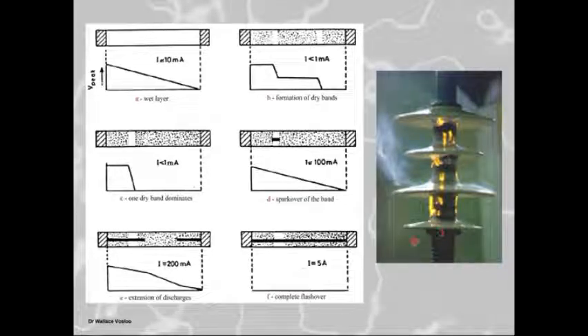But now you've got these little pollution particles which are driven by the wind, and they come boom, boom, boom, and they all start collecting onto this insulator surface. All over the surface, this pollution starts collecting. The wind is the main driver of this pollution. These wind-driven particles form a little eddy and sit in there, start forming around the rod, because this is a shed and this is a rod, and this is an alternating shed profile: large diameter, small diameter, large diameter, small diameter. The spacing to shed projection ratios are important, but you'll learn that later, okay?